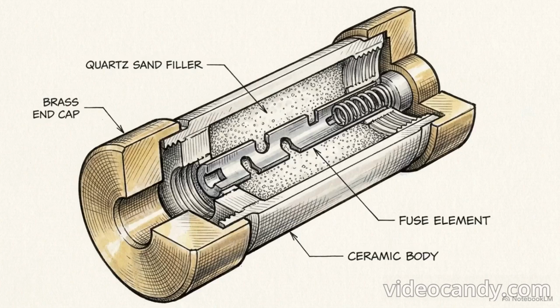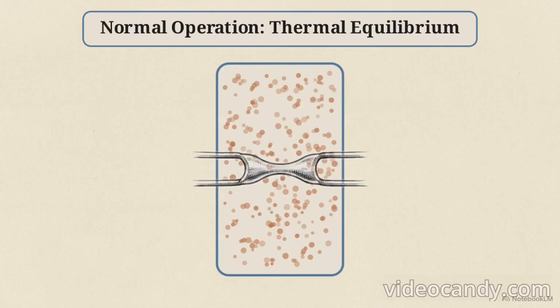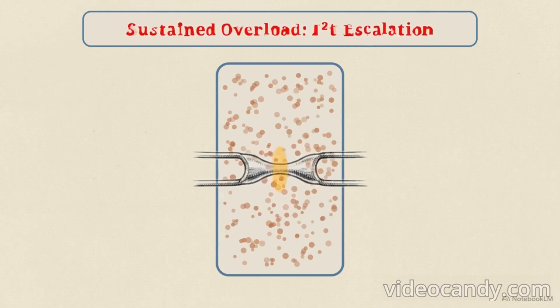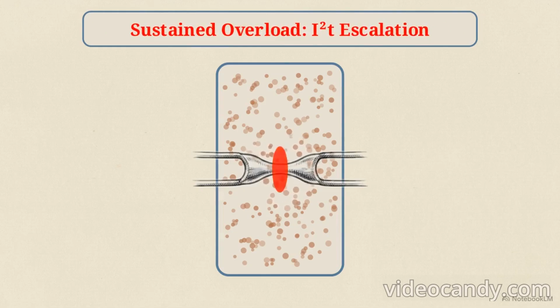During normal operation, the heat generated by the element is safely absorbed by a filler material packed inside the fuse casing, typically porous quartz sand, which conducts the thermal energy away into the surrounding air, allowing harmless loads to run continuously. But if we overload a circuit by plugging in too many devices simultaneously, the system enters a sustained overcurrent fault. The heat generated exceeds the rate at which the surrounding sand can dissipate it. It crosses the element's specific thermal energy capability, its I²T rating, and the metal wire begins to glow.